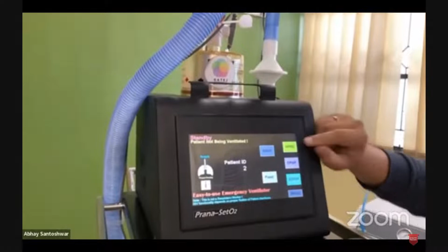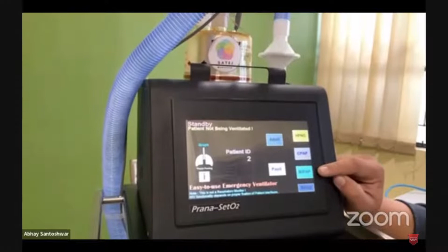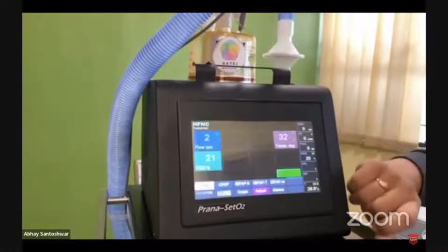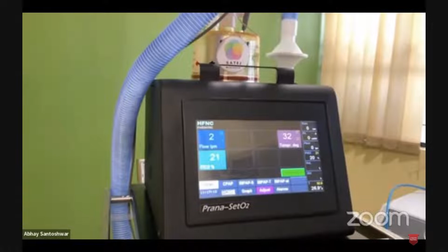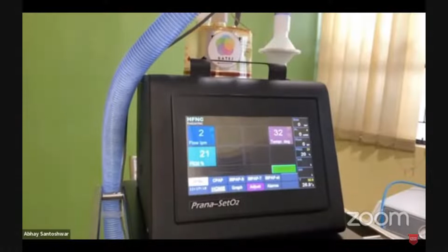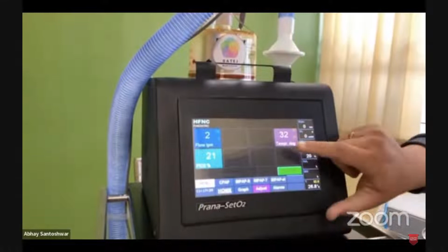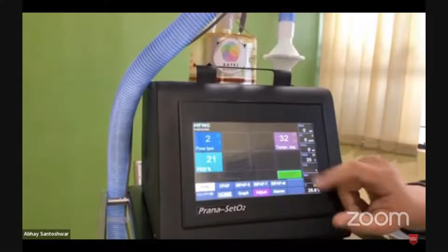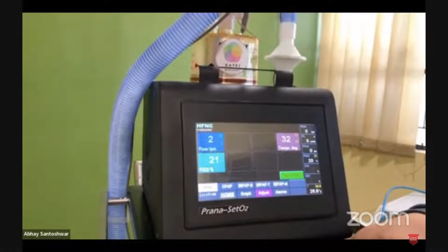So the moment she has selected the tubing, all my modes have got activated, wherein you have the HFNC, CPAP, BiPAP modes being shown on the screen. I would ask my colleague to select the HFNC mode first. Now, typically, every mode has its specific adjustments, so only those adjustments are seen live. So here in the HFNC mode, you have the flow, the FiO2, and the temperature. The temperature setting is additional compared to other ventilators, because you are adjusting the humidifier settings also through the same equipment. So this becomes very handy. Times of COVID, we wanted machines to have least settings. Even otherwise, I would suggest that with least settings, people would prefer using those equipments.